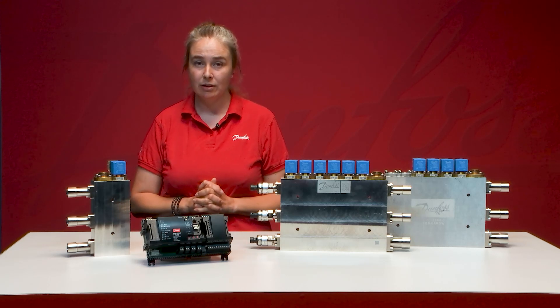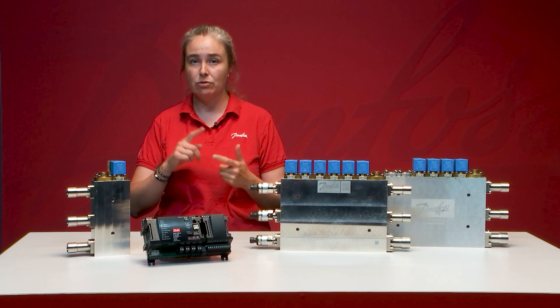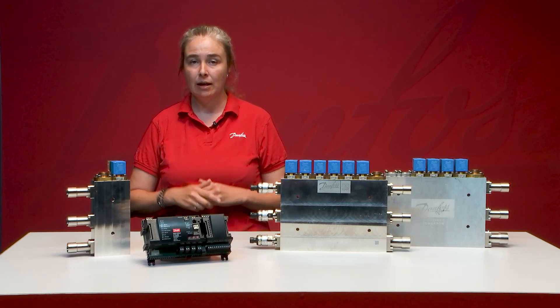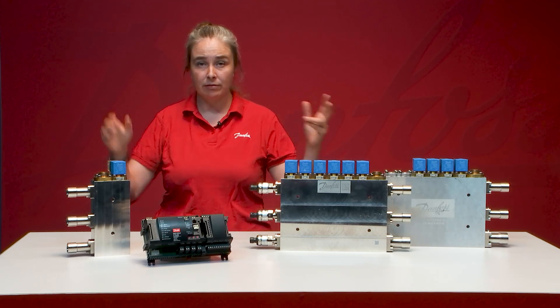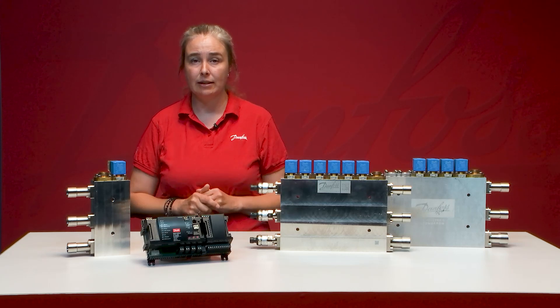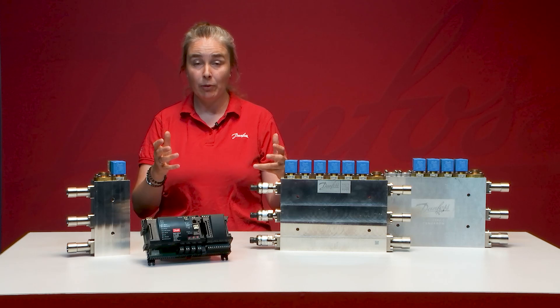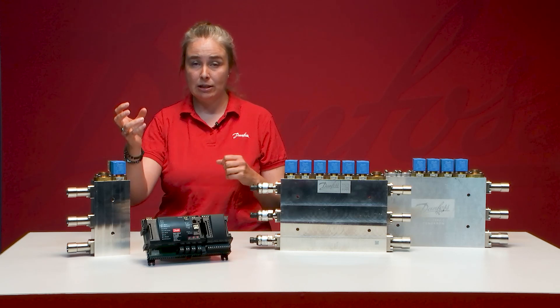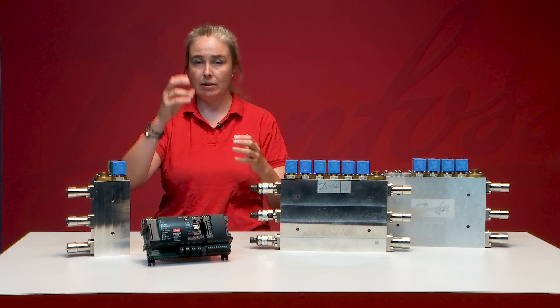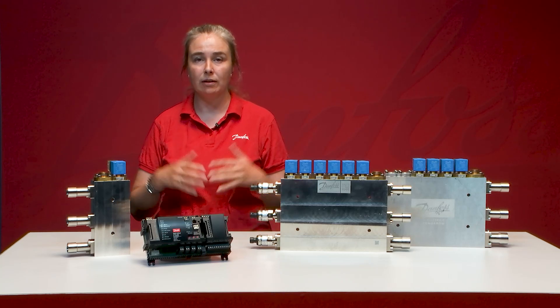Another thing to mention when we talk about liquid ejector is CALM — CO2 Adaptive Liquid Management. It ensures coordination across the system. It starts with the AK-CC55 case controller, which allows ALC superheat in all of the evaporators. It also ensures coordination between the case controller, pack controller, and the system manager, so the whole system is running at its best and supporting CALM.